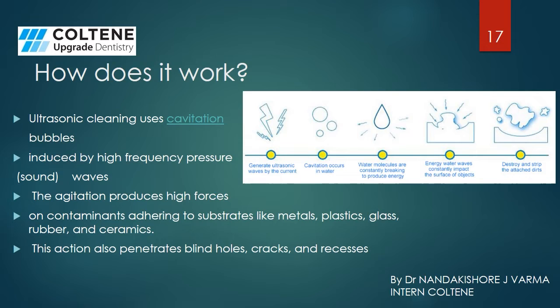Let's see how this instrument or equipment works. It uses cavitation bubbles, induced by high frequency pressure. The agitation produces high forces on contaminants adhering to substrates like metal, plastic, glass, rubber, ceramics, etc. This action also penetrates blind holes, cracks, and recesses. In short, these ultrasound waves agitate the liquid and cause cavitation bubbles to form, which have high frequency pressure and blast on the surface of the materials or instruments placed in it, causing a high force on the substrate adhering to these instruments, causing it to separate from the instrument.